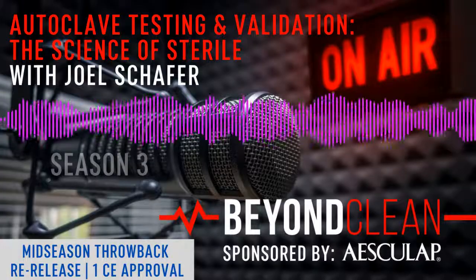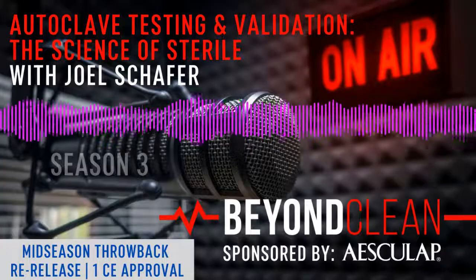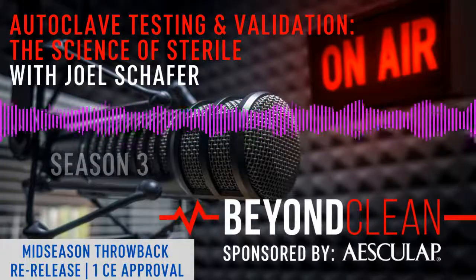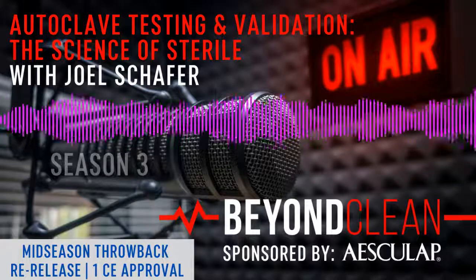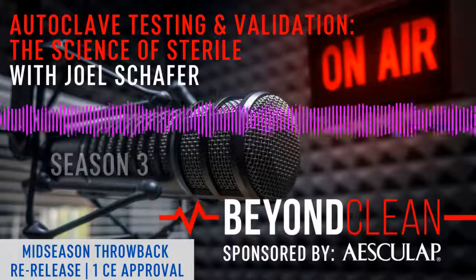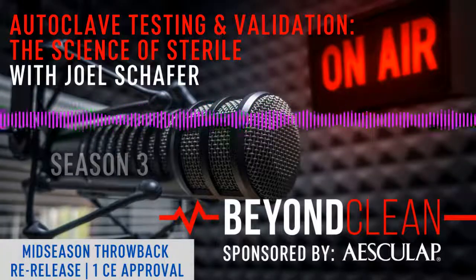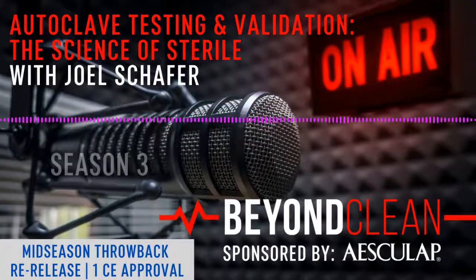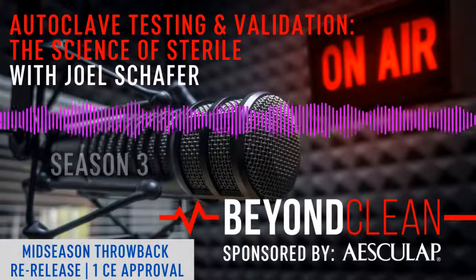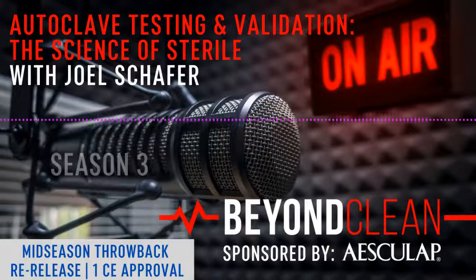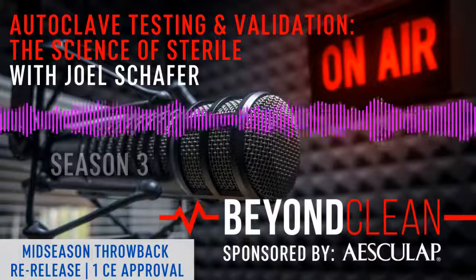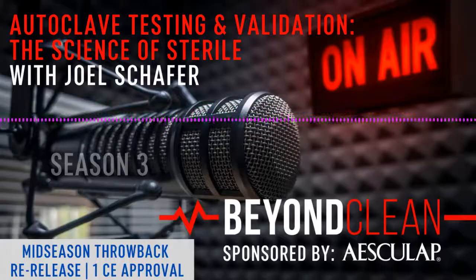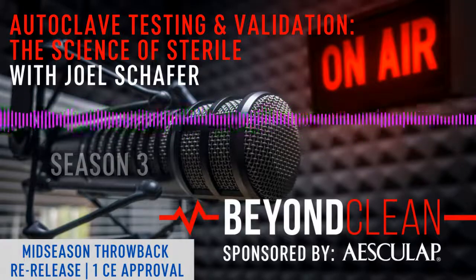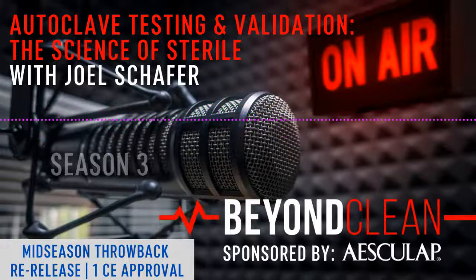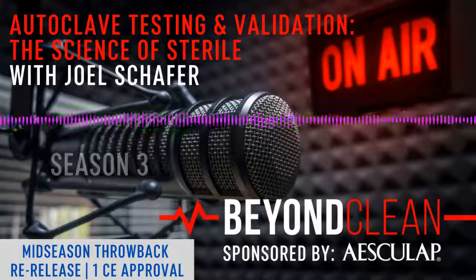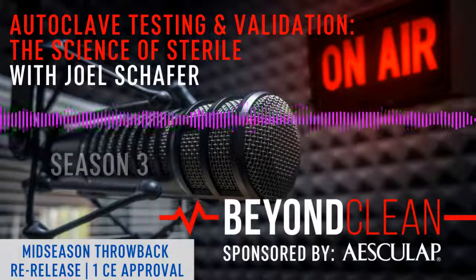Yes, I would start off by listening to the 2-part podcast that you guys did with Jonathan Wilder. I learned a ton from that, and I'm sure everybody else will as well. You could definitely reach out to my company or any other company that you may find that does the same type of validation. My question would be to the facilities people, where are you testing the steam at? Because you may be testing it right there at the boiler, but that steam has to travel through all these pipes to get to my autoclave. And how do you know the end result is the same as where it starts? Because honestly, that's where it's important. That steam may be going to the kitchen, maybe going to the laundry, and to the sterile processing department. And in my opinion, the most important customer is the sterile processing department.